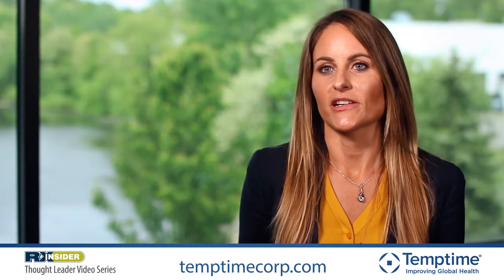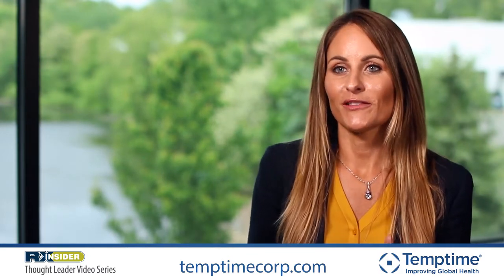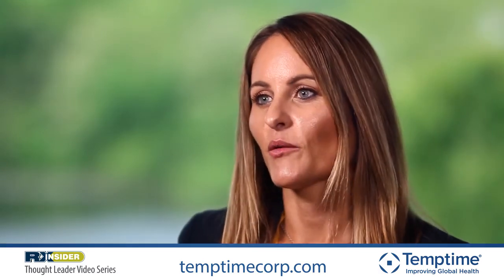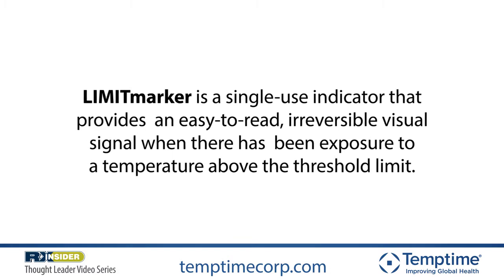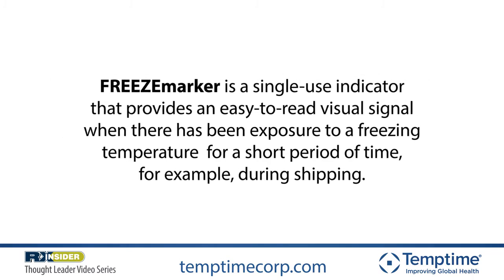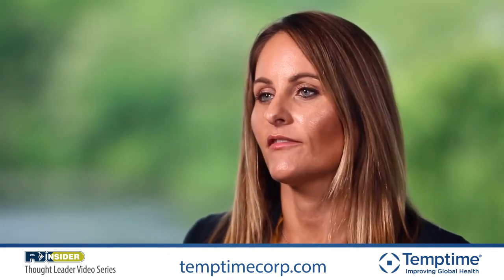A lot of times we get phone calls from patients who want to do some type of home test on the indicator to ensure it's working. Often they do what we call torture tests, which involves placing the heat indicator in the oven, microwave, or over an open flame. That doesn't replicate a real-life shipping scenario and permanently damages the indicator. The best way to do a home test of the limit marker heat indicator is to place it in your pocket and walk around the house for an hour, then check it visually and again at two hours. For the freeze indicator, place it in your standard freezer at home, leave it undisturbed for about 45 minutes, and then visually check it.